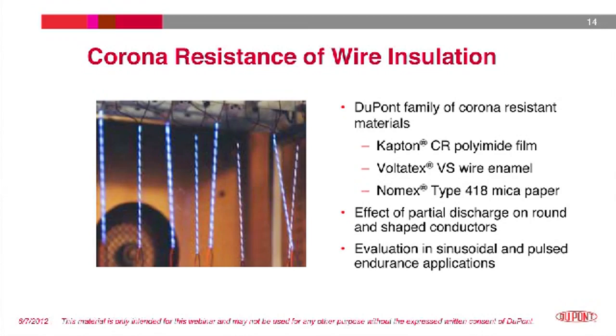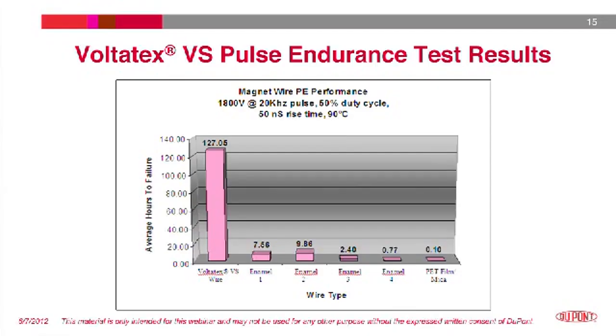For example, for small round wire used in lower voltage equipment, a corona-resistant wire enamel such as Voltatex VS is optimum due to the ease of enamel coating round wire. As wire sizes increase or become rectangular in shape, a wrapped solution such as Kapton CR or Type 418 Nomex mica paper becomes a more attractive solution. DuPont engineers are working with equipment designers to help solve their design problems. For most inverter duty motors, small, round enamel coated wire is used.